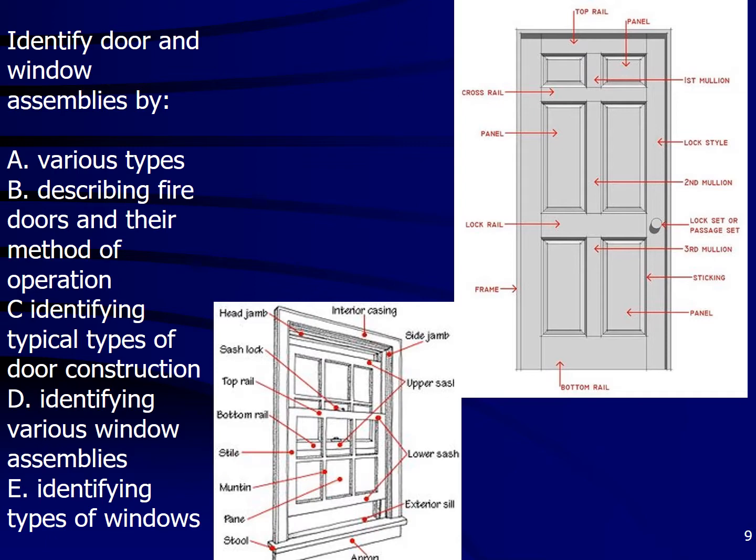The way these fire doors work is that in the event that the fire alarm goes off, the magnetic locks that hold the doors open will release and the door closes. The purpose of the door closing is to minimize airflow and to isolate smoke into an area, to ease in the evacuation of the structure.